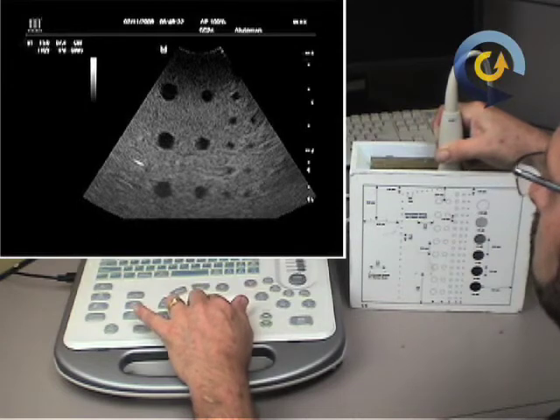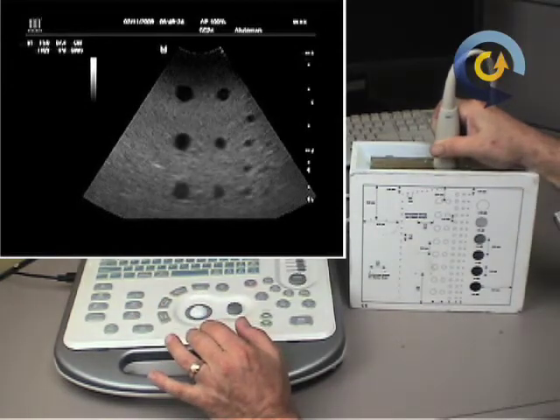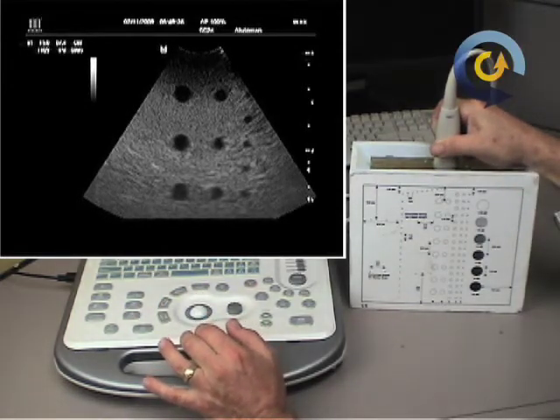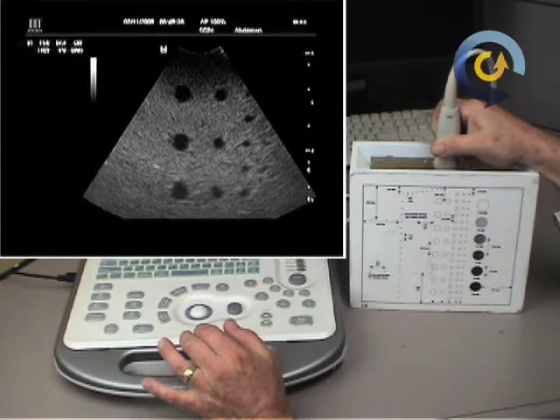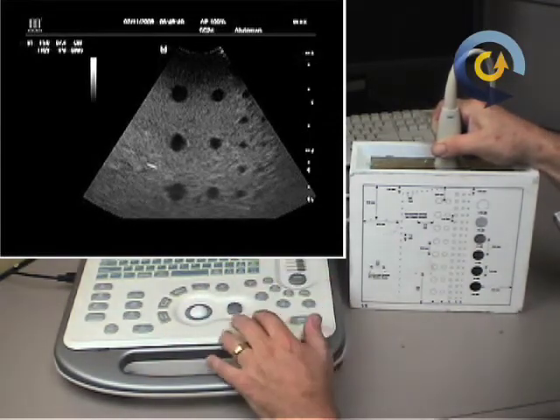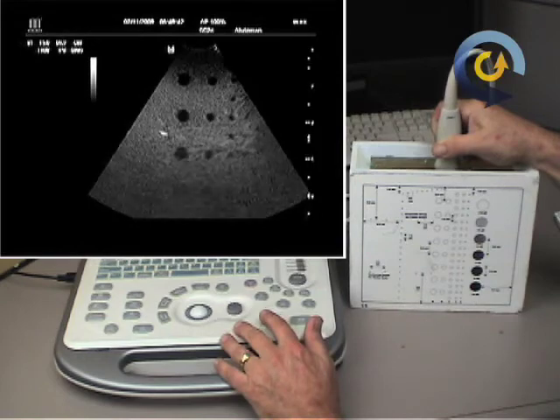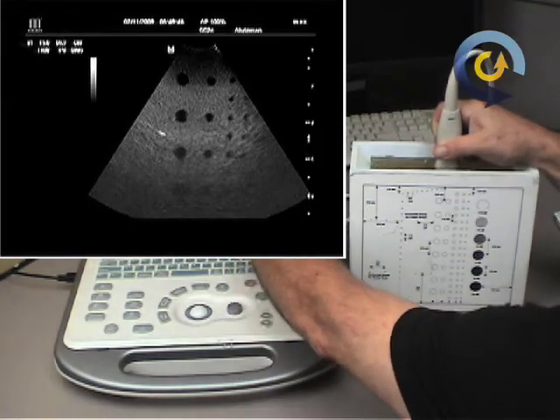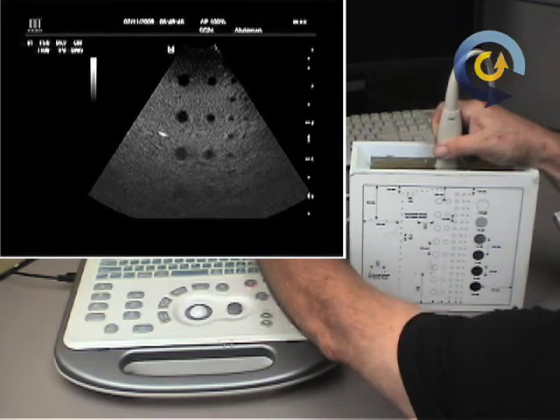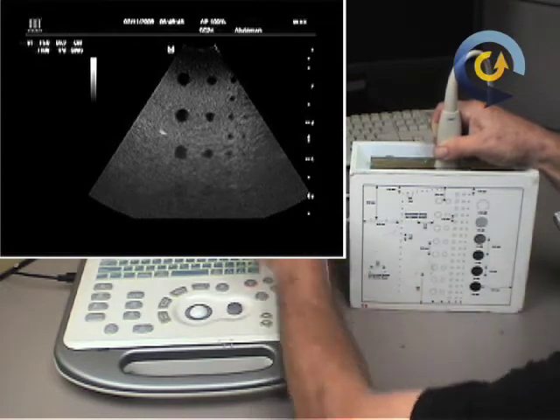If I go back over here to my frequency, and I was explaining that the transducer with a higher frequency will penetrate less in the body. That's another typical function you might want to measure. So you look at a phantom and you find out the last part where you can actually see the image before it just starts to turn to noise and you can't really see any detail.